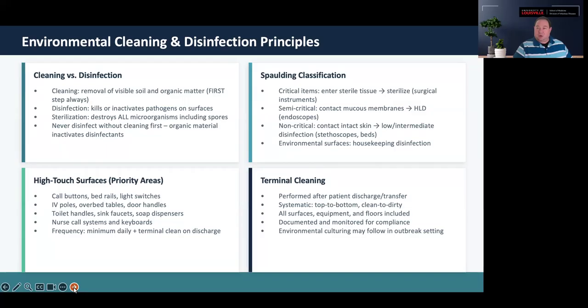So cleaning always takes place before sterilization as well, particularly with instruments, because we want to make sure that we're maintaining them appropriately. Now let's look on the right side there where you've got Spaulding's classification. This was designed years ago to help us identify how a device or a product will be used, and then what is the appropriate level of reprocessing that's needed. Now, it's not foolproof, it's not 100%, but it's about 98% accurate, which is really, really good to hold up for this many years.